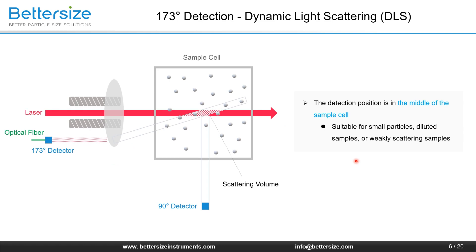Scattering volume is the intersection of the incident laser beam and the scattered light intercepted by the detector. When the detection position is in the middle of the sample cell, compared with the 90-degree design, the scattering volume is so large that the detector receives many scattering signals from the particles, increasing the sensitivity of the instrument. It has better detection ability for dilute samples with smaller sizes and weaker scattering effects. However, this detection is not suitable for samples with extremely high concentrations and very strong scattering effects, as the result will deviate from the true value.